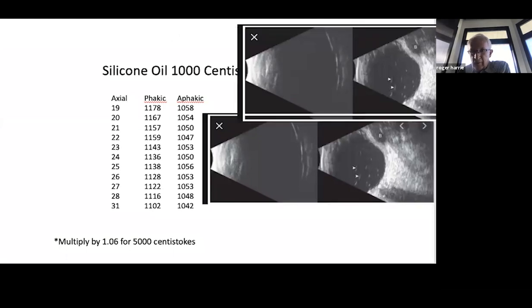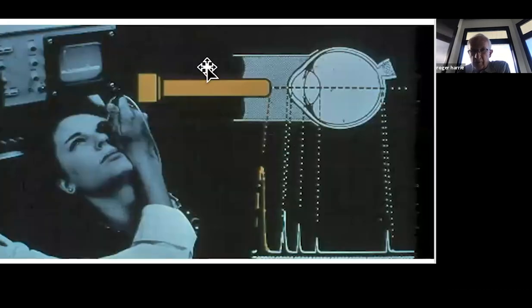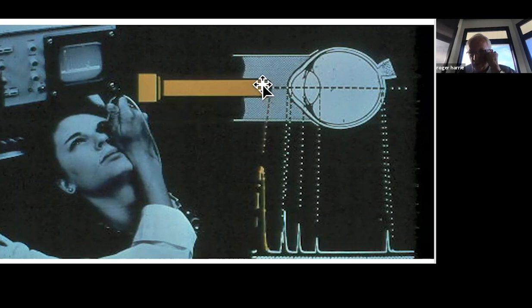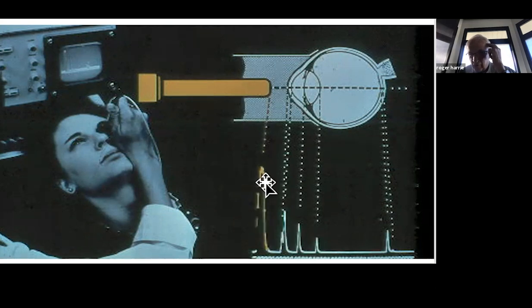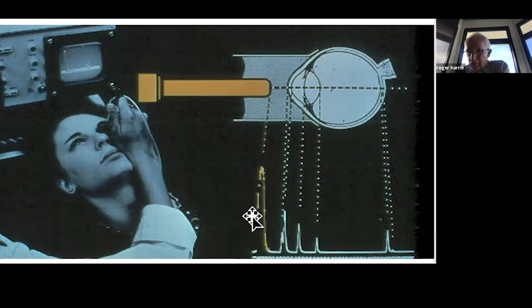The immersion A-scan display separates all anterior segment structures: the initial probe signal, then a gap through the fluid bath, then the corneal spike, anterior chamber space, anterior lens surface, posterior lens surface, vitreous, and finally the retinal spike. If the probe contacts the cornea directly, all of those anterior structures collapse into the dead zone and are indistinguishable — demonstrating why separating the probe from the cornea is essential.